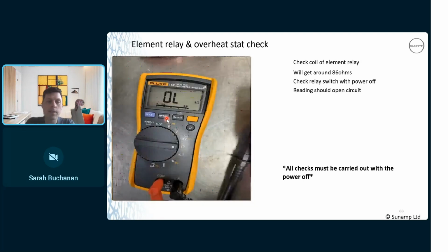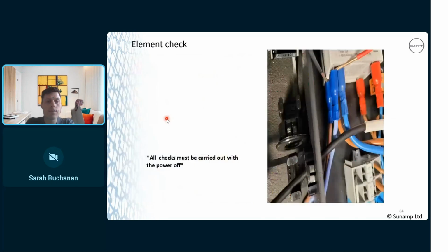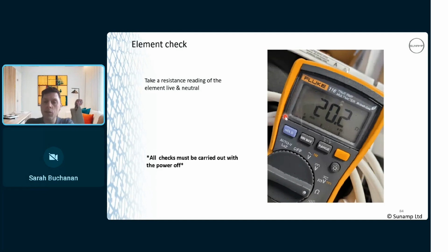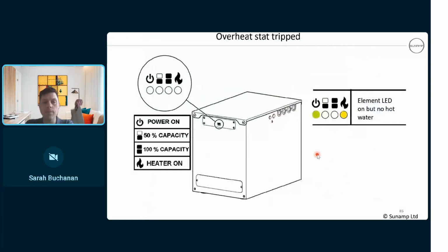All right. Yeah, resistance reading across the element, live and neutral. You're also checking your overheat stat here as well. So about 20 ohms, 18 ohms. I mean, that's plus the resistance of my leads, but between 18 and 21 ohms is what we're looking for, 22 ohms, something like that. So if you get an overheat stat tripped, that's going to be your LED scenario. Power, element, nothing's happening. The customer's got no hot water.